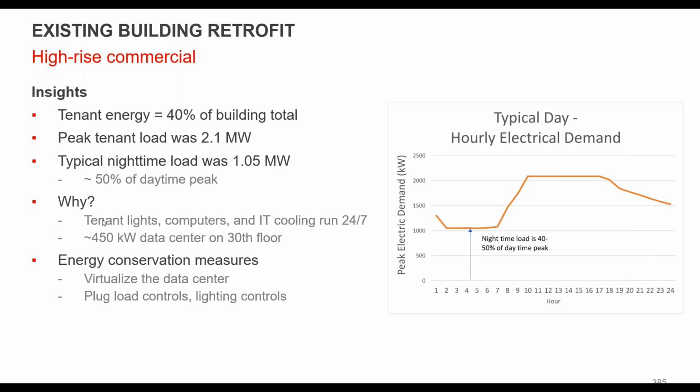And then a lot of stuff was just being left on. There was no controls on lighting. A lot of large IT equipment was running 24/7. So again, that gave us very good insight into how the building was running and creating these profile schedules.